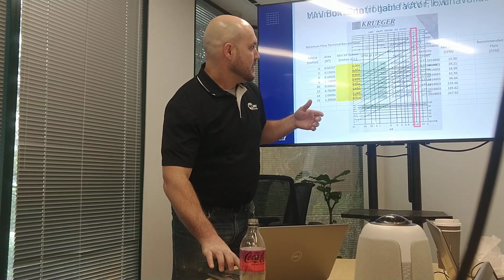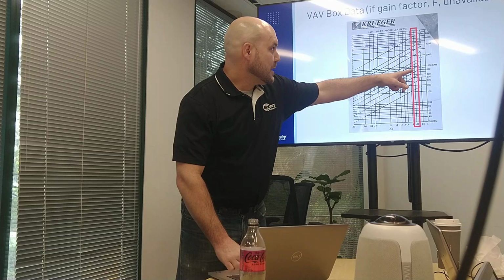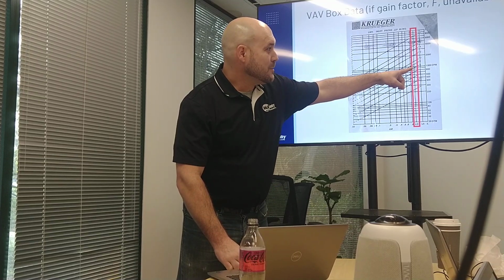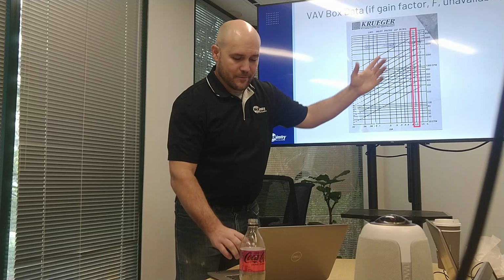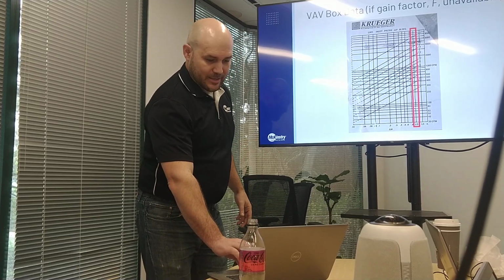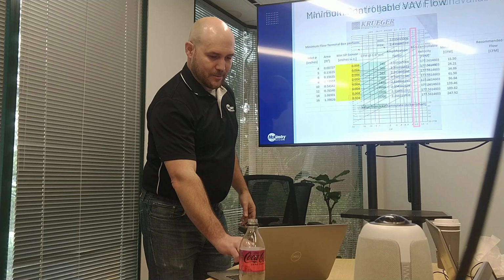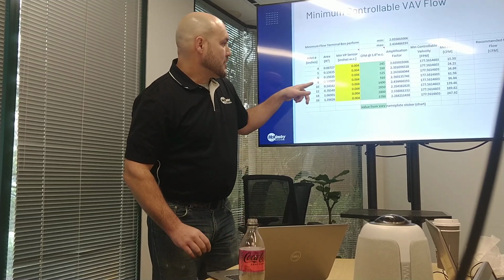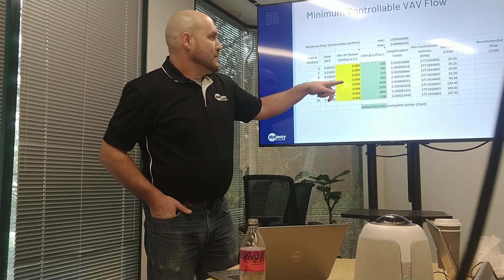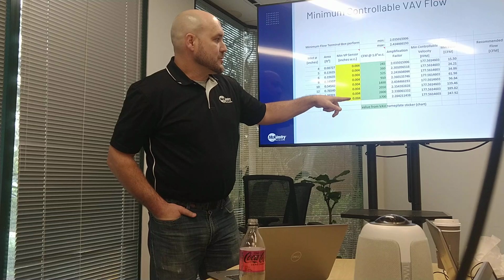It was where the actual CFMs, actually it's from this one we said, oh, this crosses, it looks like it's maybe just a shade above 900, so we'll call it 910, for example. Not an exact science when you're doing this without the values, but so we said, okay, the 8-inch box is at 910, minimum velocity pressure sensitivity of 0.004 inches. You kind of plug these numbers through. Good. It's good that the minimum controllable velocity is the same for all of these.